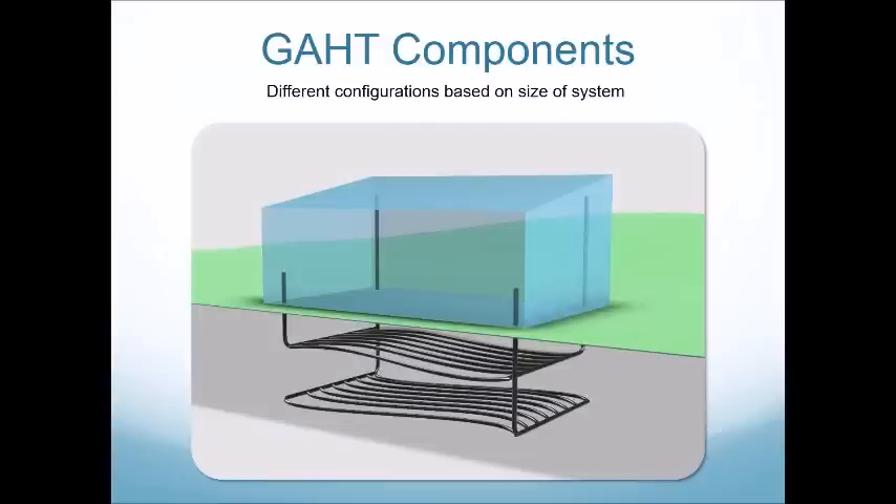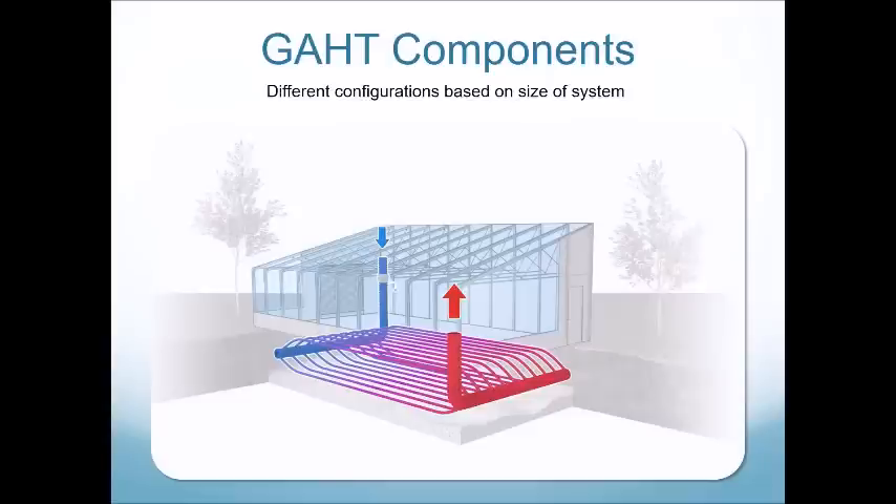The components are based on the size of the system. We generally use two different sizes: a small GAHT or residential system for residential greenhouses that require less heating and cooling, utilizing smaller diameter pipes, smaller fans, and typically two layers of pipe at two feet and four feet below grade. The large GAHT or commercial system demands more heating and cooling capacity and utilizes larger diameter pipe and much larger fans.